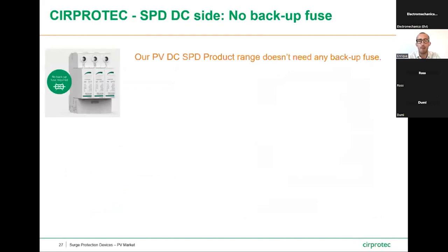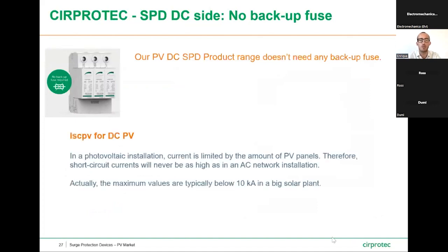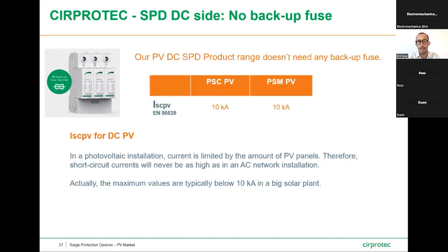One of the key value parameters of our DC product range is that our range does not require a backup fuse. In a photovoltaic installation, the current is limited by the amount of PV panels installed in the installation. Therefore, the short circuit current ratings will never be as high as in AC network installation applications. In fact, the maximum values are typically below 10 kA in a big solar plant. So, the Iscpv parameter we are declaring as 10 kA in both product ranges is enough to assure that our SPD in the PV application does not require a backup fuse.